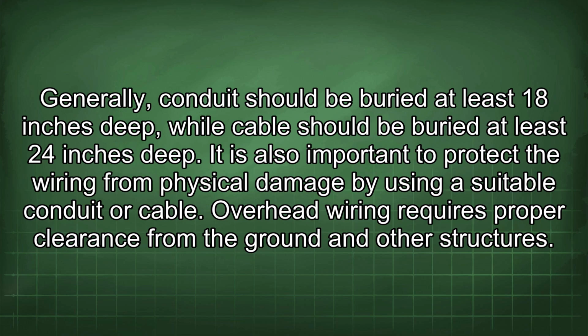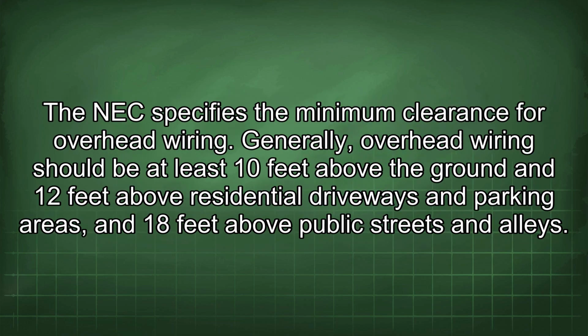Overhead wiring requires proper clearance from the ground and other structures. The NEC specifies the minimum clearance for overhead wiring. Generally, overhead wiring should be at least 10 feet above the ground and 12 feet above residential driveways and parking areas, and 18 feet above public streets and alleys.